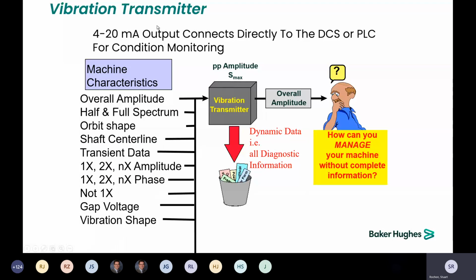Last thing we're going to talk about is transmitters. These are basically the same things that we've been talking about, but they have an extra circuit in there to convert a specific range to a 4 to 20 milliamp output. With that 4 to 20, you are only going to get the overall amplitude, which is great for watching it through a DCS or a PLC just for condition monitoring. All of them do still have the dynamic data available on the system. So you can use an ADRE or portable data collector to go out and collect all this other great data that is useful for doing diagnostics.